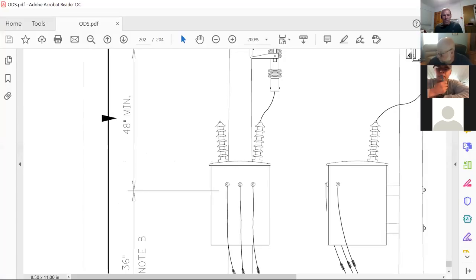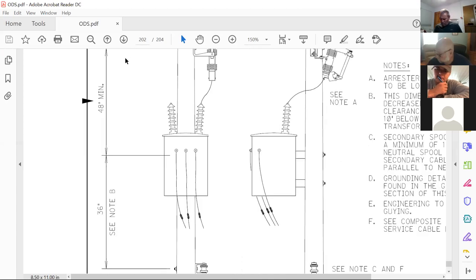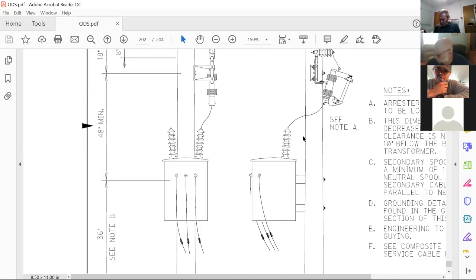Now, let's go back to, let's see, where was I? So we'll assume right here on my picture that I've got that same 25 kVA hanging right there. If you remember before, who calculated the fuse for me? It was 5 amps, right? Right, but that was at 25. This is where I'm headed, and I'm glad you threw that information in there. So you triple it, since you got triple the size, so you go 15 amps.